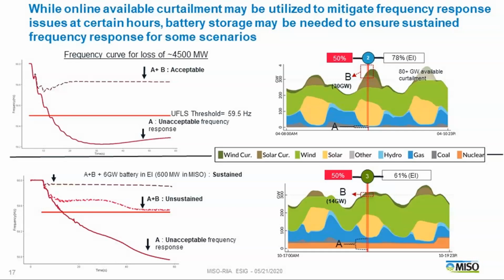When we plugged that into our model, in some conditions there was enough natural curtailment on the system, due to either overgeneration or bottling up of the resource, that the renewable resources themselves were able to arrest the fall in frequency and bring it back to a stable level. So you have natural trade-offs or co-benefits of curtailment due to other causes. But this isn't always the case—you can't always rely on curtailment being available to meet our frequency response needs.